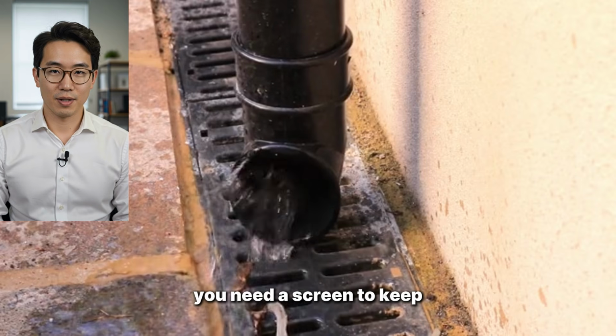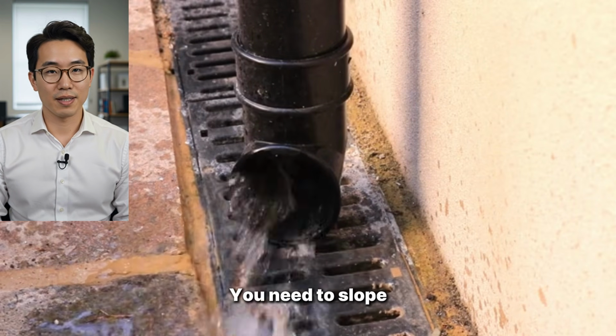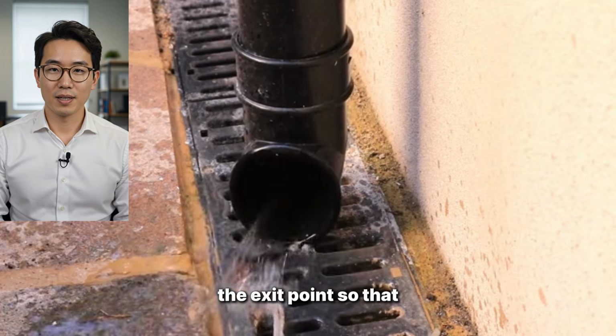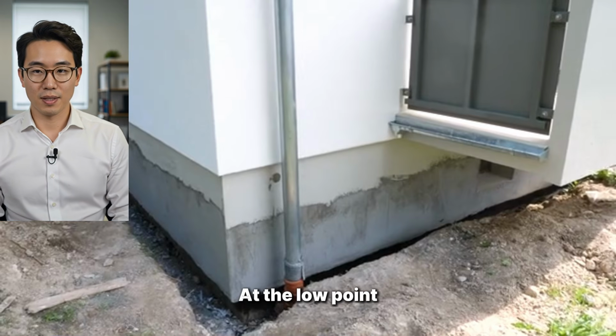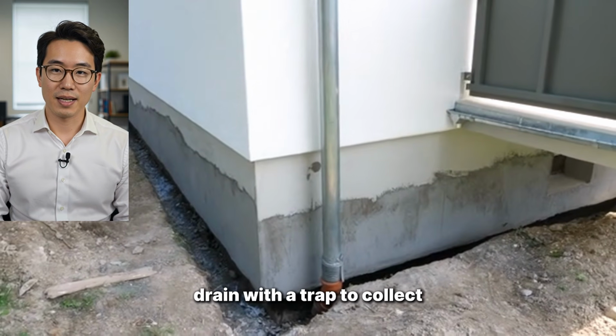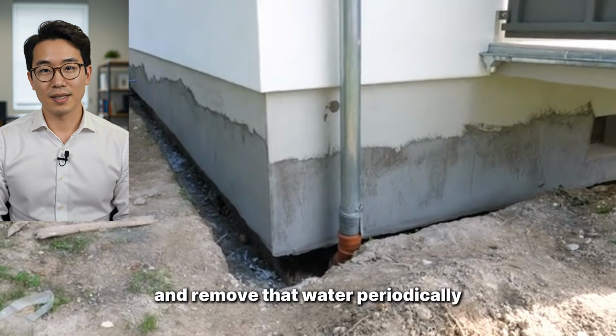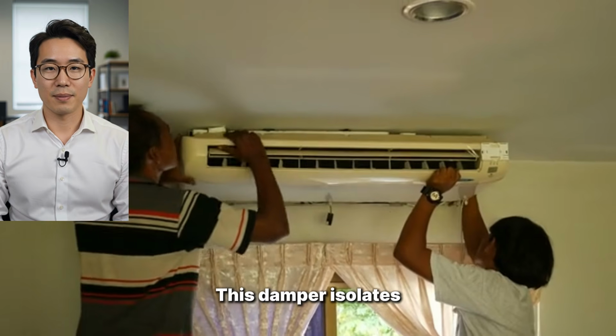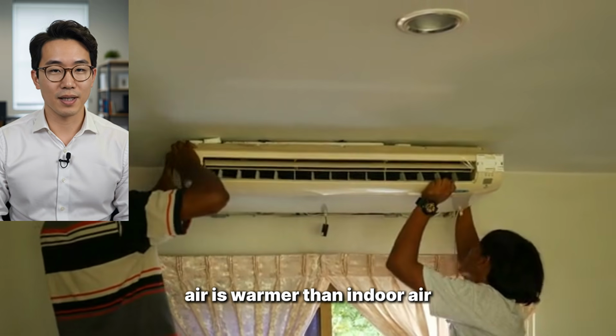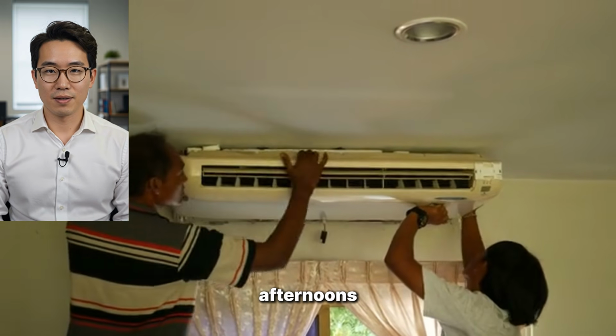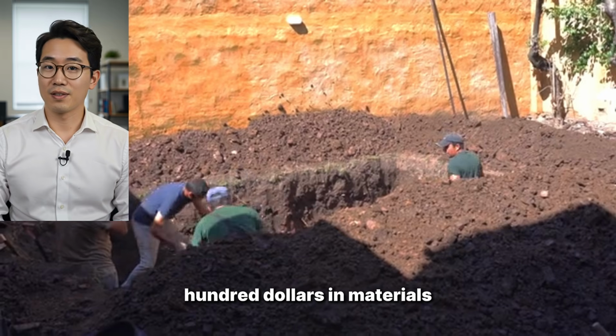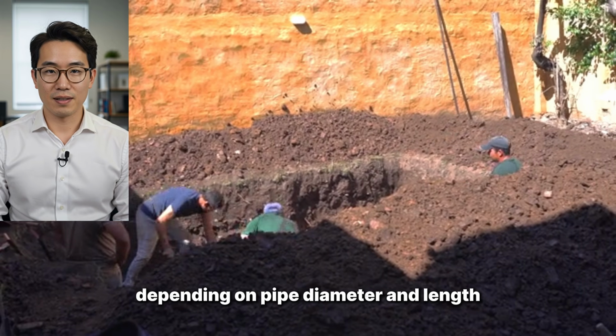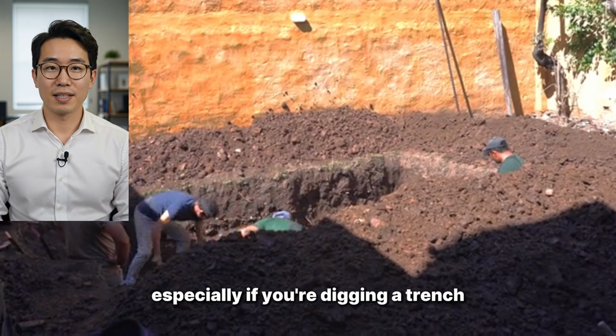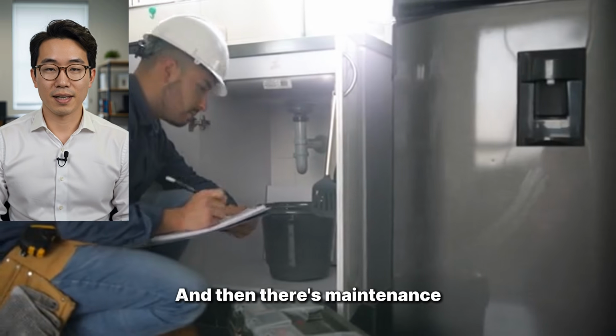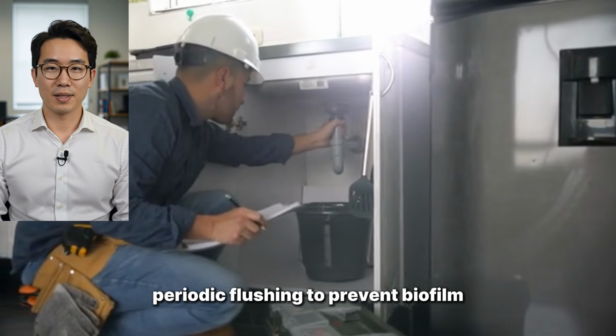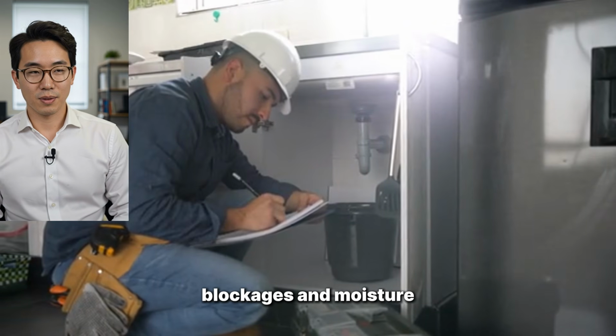At the intake, you need a screen to keep animals and large debris out. You need to slope the pipe slightly toward the exit point so that condensation water can drain. At the low point, you typically install a small drain with a trap to collect and remove that water periodically. At the house end, you need a damper. This damper isolates the system when outdoor air is warmer than indoor air. Otherwise, you'd pump heat into the house in summer afternoons. The whole thing might cost $50 to $300 in materials, depending on pipe diameter and length. Labor is the real cost, especially if you're digging a trench through clay or rock. And then there's maintenance. Periodic flushing to prevent biofilm, checking drainage, inspecting for blockages and moisture accumulation.